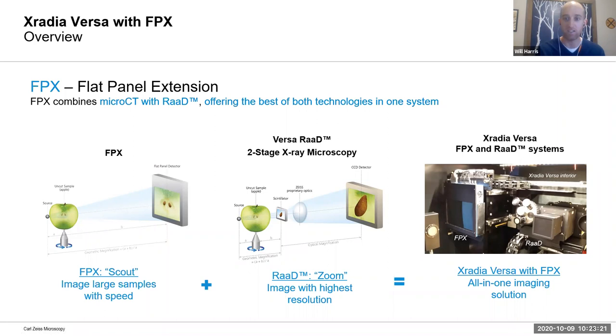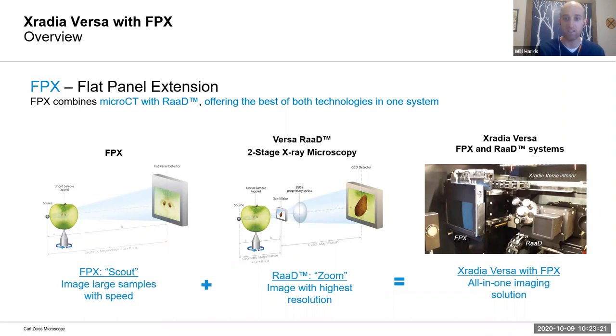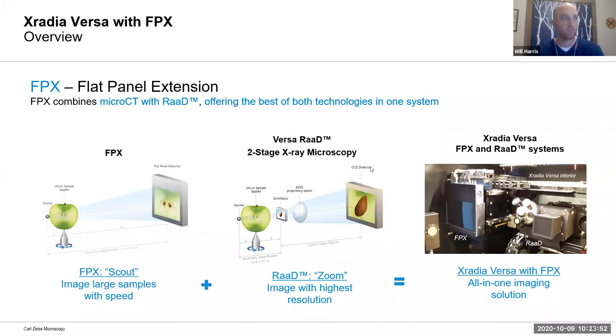It turns out if you combine both types of technologies, you get the best of both worlds. Traditional designs are good at looking at things with a speed advantage, and the instrument coming to Florida will actually have both the advanced optical detector design as well as a flat panel detector integrated — this covers the broad spectrum from pretty big objects down to small things at super high resolution.